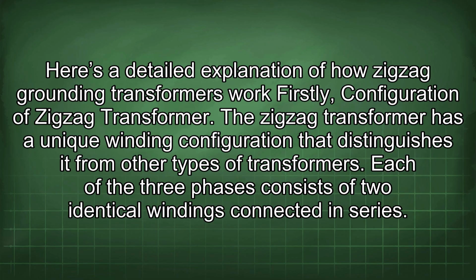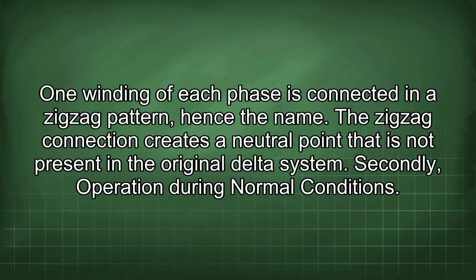Firstly, configuration of zigzag transformer. The zigzag transformer has a unique winding configuration that distinguishes it from other types of transformers. Each of the three phases consists of two identical windings connected in series. One winding of each phase is connected in a zigzag pattern, hence the name. The zigzag connection creates a neutral point that is not present in the original delta system.